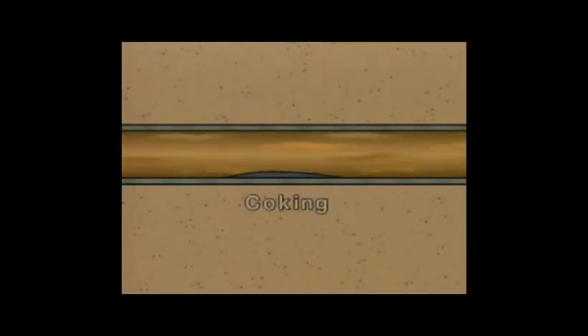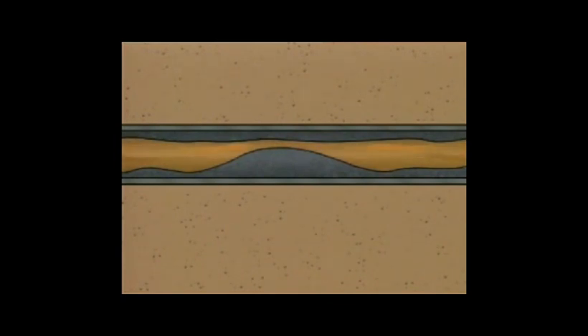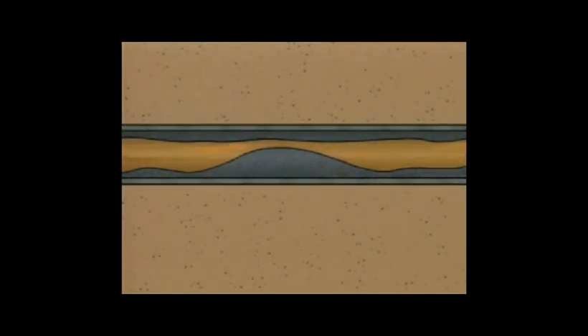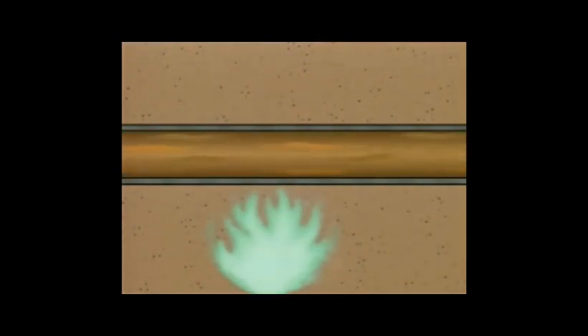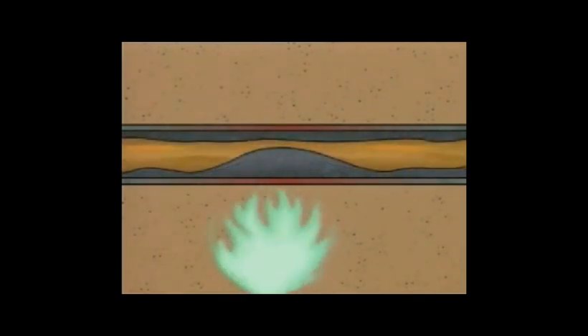One problem that can occur is coking — the accumulation of carbon deposits on the inside walls of tubes. Crude oil and some process fluids leave carbon deposits as they are heated and flow through the tubes. Coking reduces the inside diameter of tubes, restricts fluid flow, and reduces heat transfer by insulating the tube walls. If not corrected, the tube could overheat, weaken, and eventually rupture. Coking can also develop when burner flames contact the tubes — a problem called impingement — which creates hot spots and carbon deposits that can also lead to tube rupture.